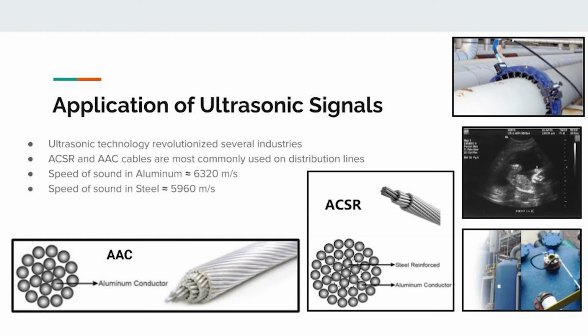A majority of modern distribution lines are made of all aluminum or aluminum conductors with a steel core. Although we know the typical speed of sound in these materials, we do not know how the ultrasonic waves will respond to the braided conductor. There has been no research or testing on this subject, so we will be doing physical experiments on our distribution line model. Our goal is to understand the characteristics of this ultrasonic wave in an all-aluminum conductor distribution line.